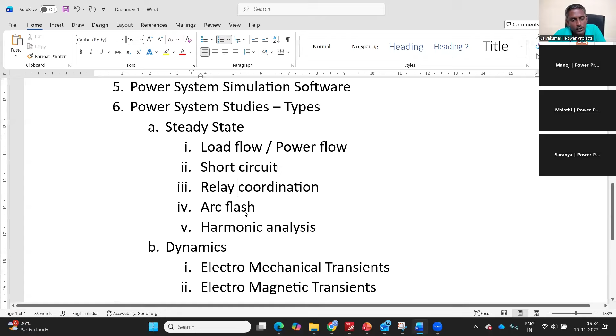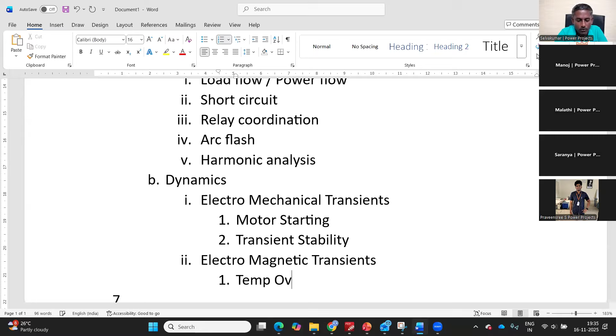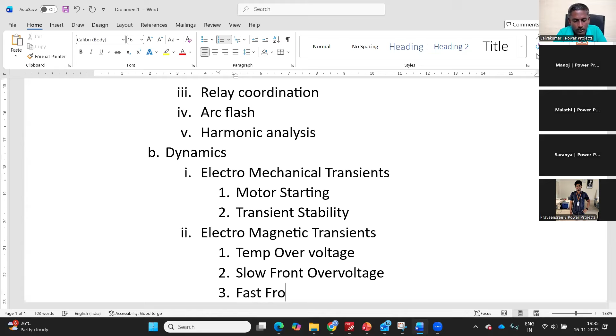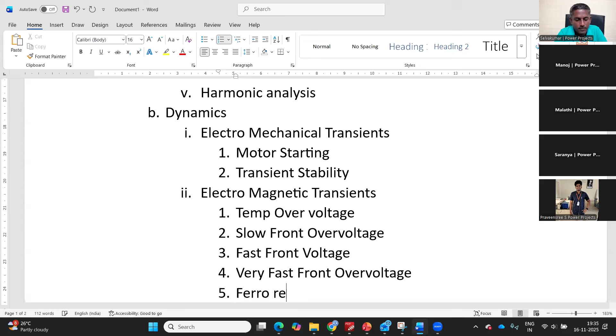Dynamics is further classified into electromechanical transients and electromagnetic transients. Electromechanical transients include things like motor starting or motor acceleration study and transient stability. Electromagnetic transients are further classified into temporary overvoltage, slow front overvoltage, fast front overvoltage, very fast front overvoltage, ferroresonance, and transient recovery voltage.